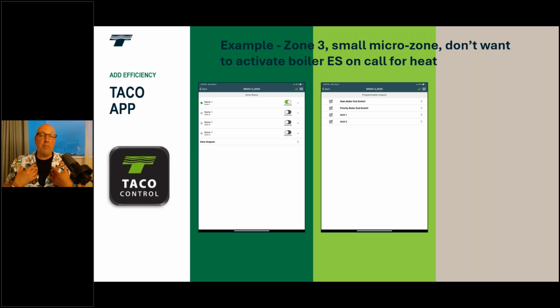And like in my own house right now, I've got 7 zones. I have the guest bath, hallway, and laundry room on the 2nd floor as a zone that has no exterior walls, all radiant floor heating. And so if that is the only zone to call for heat, the boiler is going to short cycle like mad because it's not extracting that many BTUs out of it. So the boiler just bangs on and off if that calls for heat.